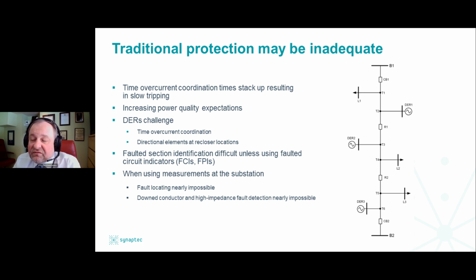locations. Faulted section identification is very difficult unless you use the faulted circuit indicators, or as some of you may know them, fault passage indicators. And when using measurements at the substation, locating is nearly impossible. And I would argue down conductor and high impedance fault detection is nearly impossible. Those feeder relays located at substations kind of fight the fight with one hand tied behind their back.